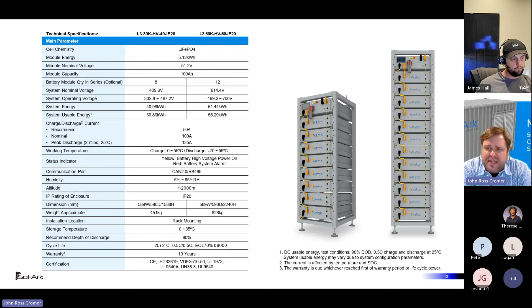The outdoor cabinet uses the same battery modules. It just has a more robust case with an air conditioner unit built into it that air conditions the batteries. We make the air conditioner too. We make everything that's in our product line. The gotcha of the outdoor system is that we constrain the system size to 6 inverters and 6 battery cabinets per inverter. So you can build a much larger system indoors than you can outdoors.